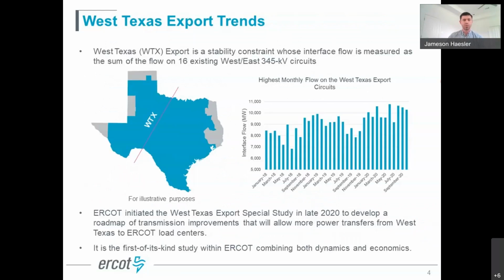Zooming in a little to the West Texas export constraint specifically—as touched on earlier, it's a stability constraint made up of an interface consisting of 16 west-east, east-west, 345 kV double circuits, and we measure the flow across all of those lines. As the generation trends from the previous slide have started to manifest, we see that result as we monitor flow across the West Texas interface. This only goes up to the end of 2020, but in 2021 the trends continue, and we see a steady but consistent increase of flow across that interface.